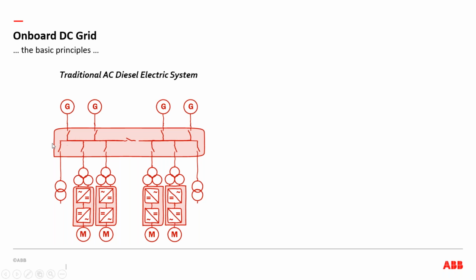On either end you have a transformer going off to power your hotel loads, auxiliary loads, pumps, lights, plugs. But in the middle you have your dominant loads, the 4 propulsion motors. In this case, we have a 3-phase transformer going to the variable frequency drive, which goes from AC to DC, then DC back to AC, and out to the motor. That's your conventional diesel electric arrangement.